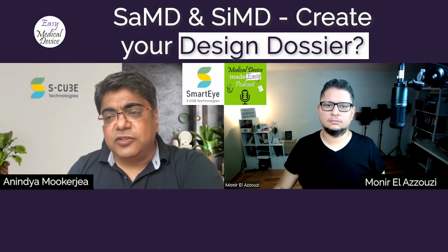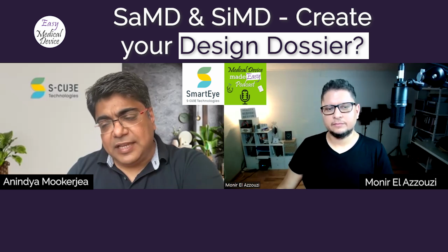Now, to come back to your second question, if they are late: it's never late until you are touched upon by the audit, or even if you are audited and it's an initial stage one where you learn that you had to do many things in terms of the software design file and you haven't, yes, you can still do it. Three important activities that we suggest in software as a medical device or software in a medical device are safety, which is risk, security, which is cybersecurity, and human factors, which is also usability.